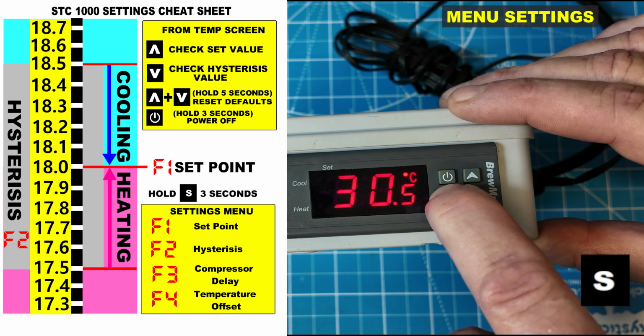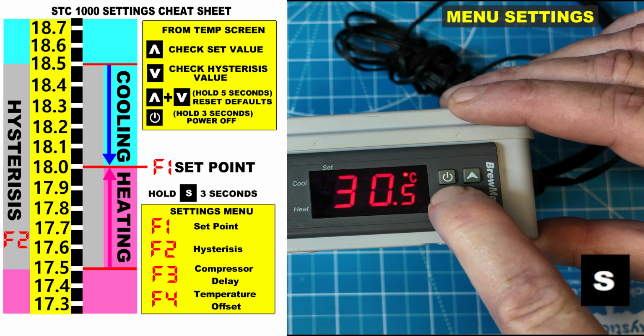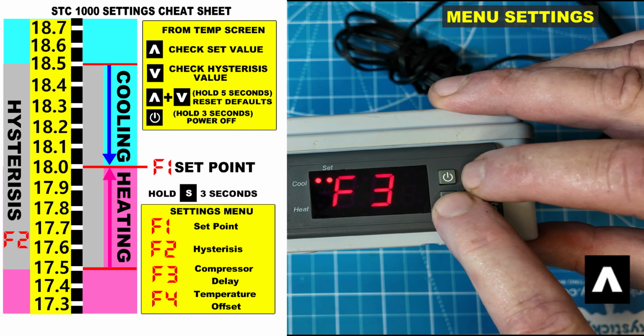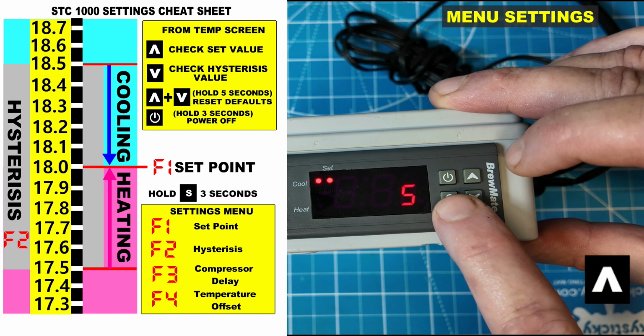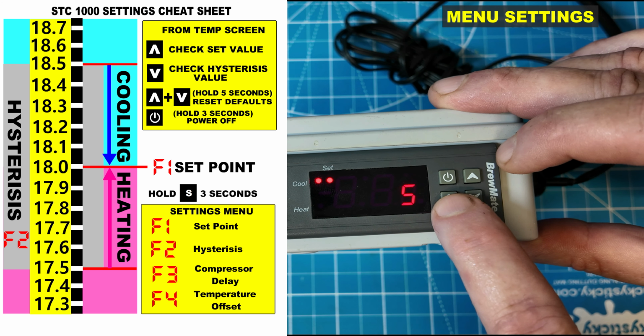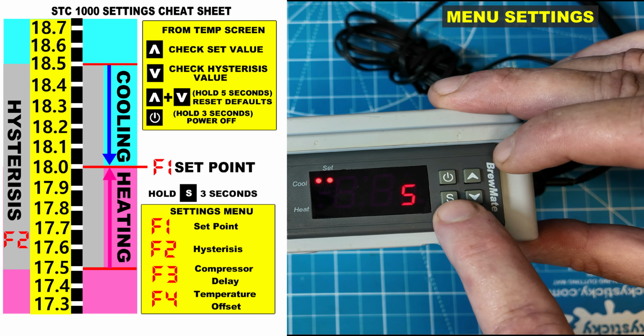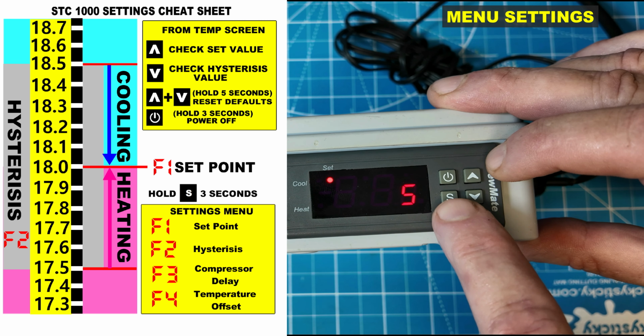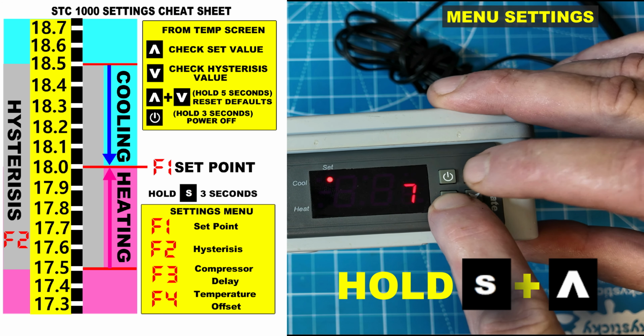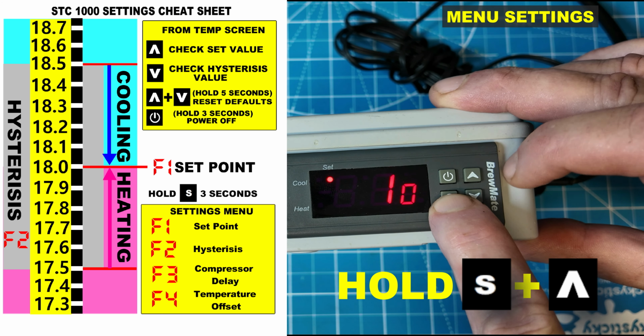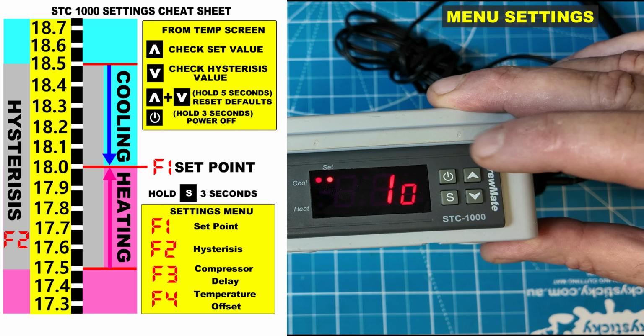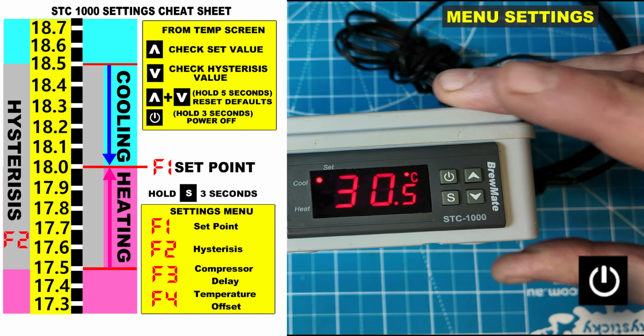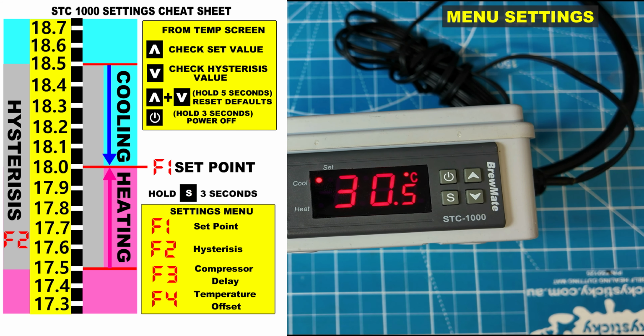Again, back in, we'll have a look at F3. This is your maximum cooling delay. You can see it's set at 5, that's 5 minutes. Honestly, that's pretty good, but if we wanted to change it, we can go up to 10. We want to lock in 10. You can hit the power button and back to the main menu.